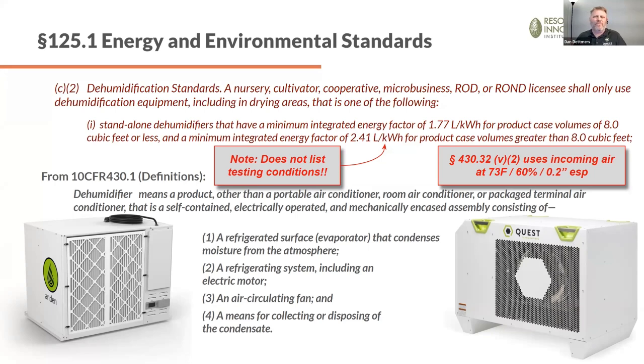So this is the equivalent of when you buy a car and you get your miles per gallon - rated city and rated highway. There's a very specific test they have to go through to get that number, so it's an apples to apples comparison. Likewise, make sure when you're doing your apples to apples comparison on standalone dehumidifiers, that it's at these numbers. If I were to test this at 80 degrees, 60 or 80% or even higher, you can imagine warm, humid air coming into a dehumidifier means I'm going to get a lot more water out of it, and it's going to be much more efficient.